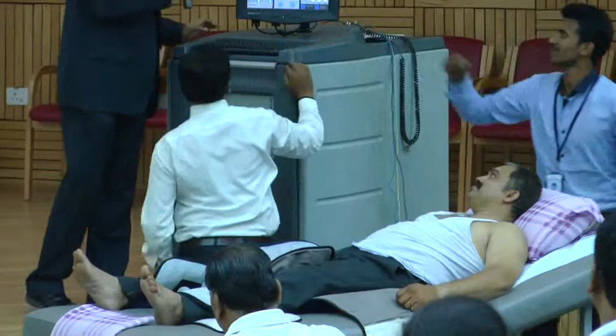So the marker you are seeing is actually we can control when we can inflate and when we can deflate the cuff. So the inflation and deflation can be manual or it can be in the auto mode. So same as IABP, the inflation happens exactly during the diastolic phase, and the deflation of the cuff occurs during the systolic phase. So you can see the QRS complex. The first one is the inflation and it ends in the deflation. The blue mark shows how much time the cuff is kept inflated.